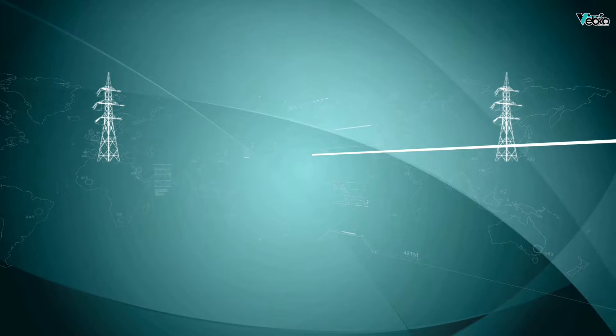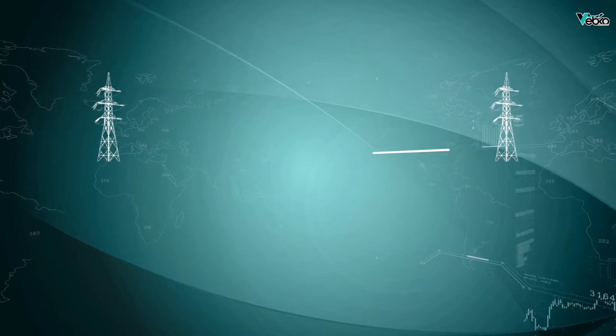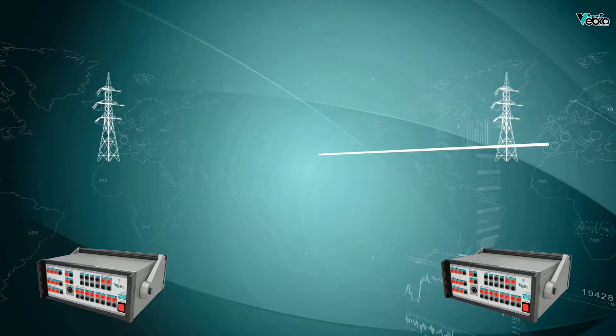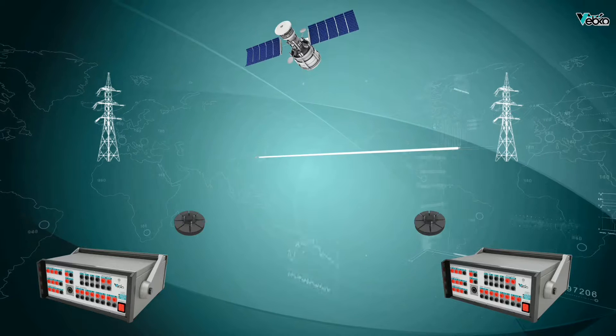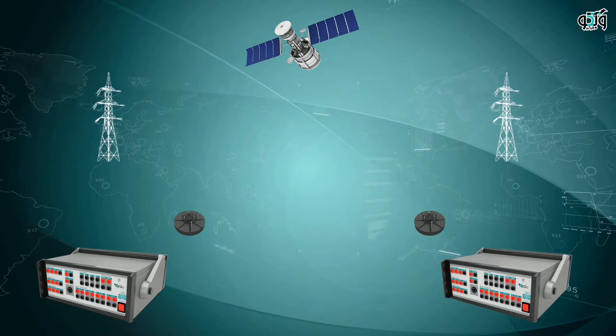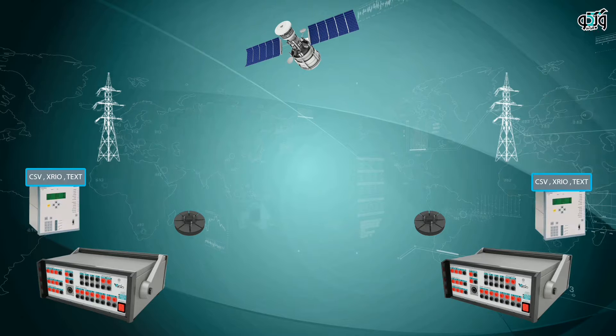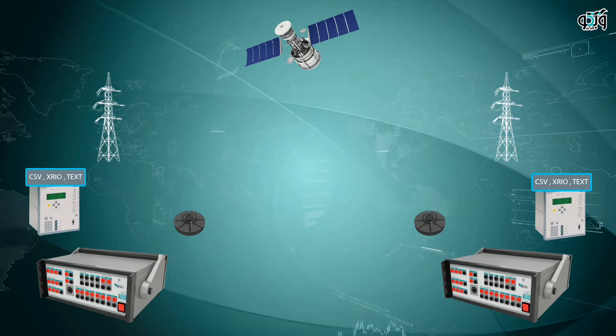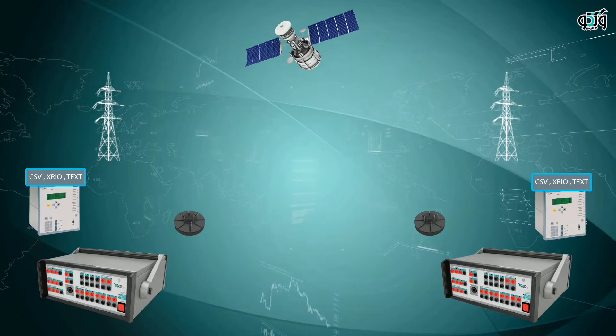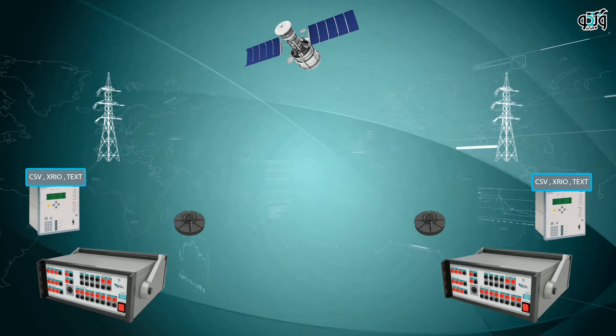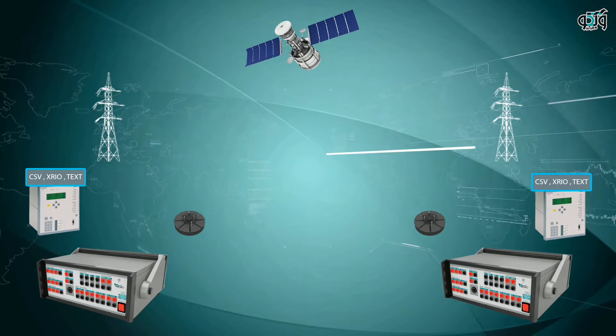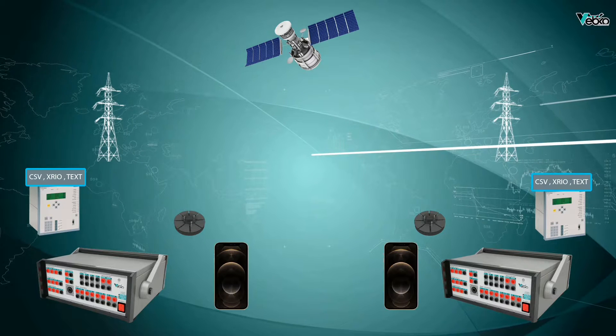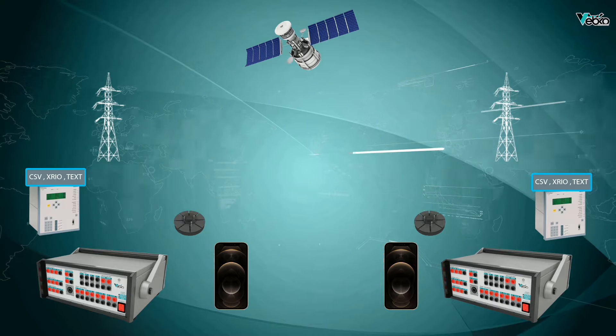A test device on each side, a hardware piece to synchronize the two devices like a GPS satellite, a file that is exported from the relay software to be used in the test device. This file can be of CSV, XRIO, text or other formats. A communication equipment such as a phone or a two-way radio to communicate with the other posts.